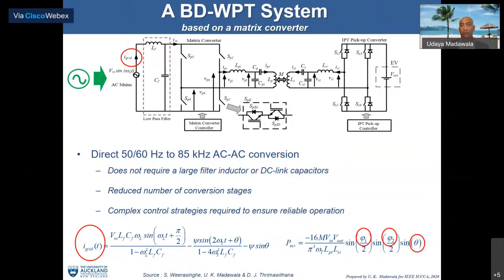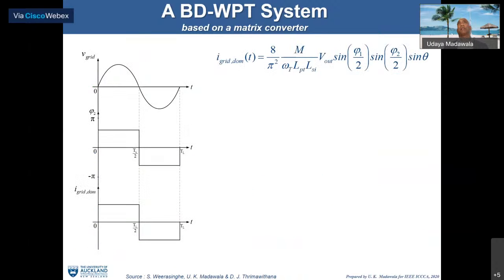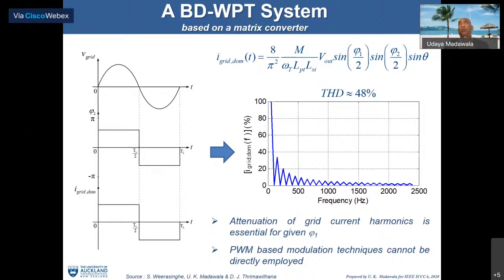So how do we do that? Looking at the grid current equation I showed, if we lock into phi1 or phi2 and theta with square wave modulation, you can see the amount of harmonics generated. The THD is very high, around 48%, which doesn't comply with the standard.